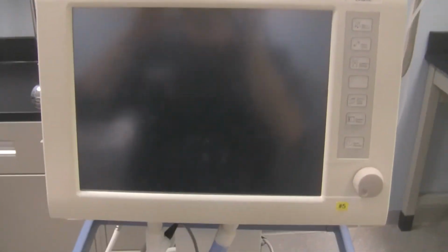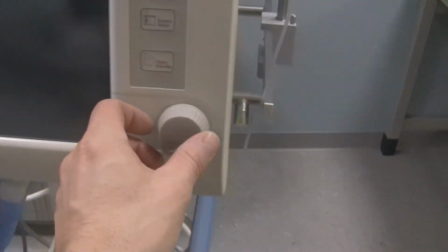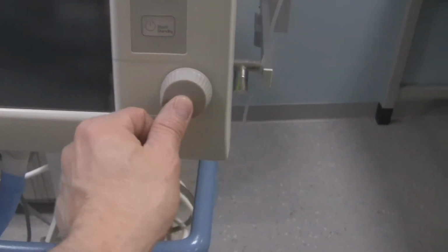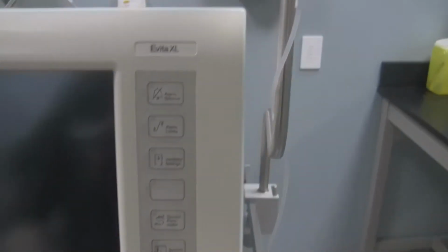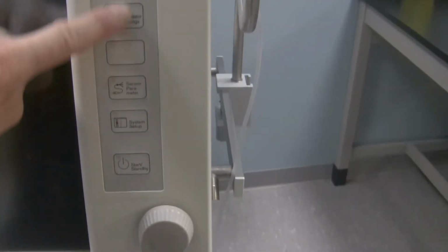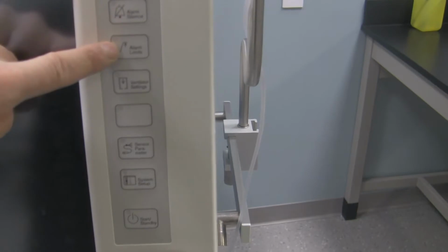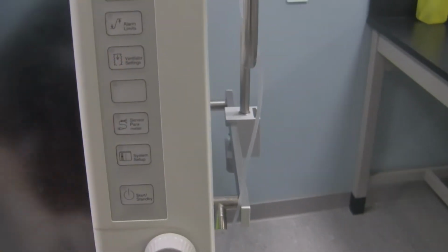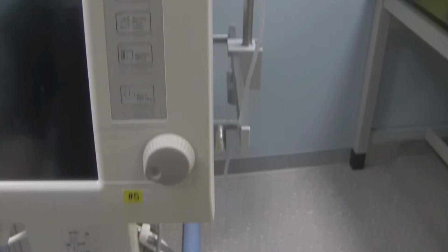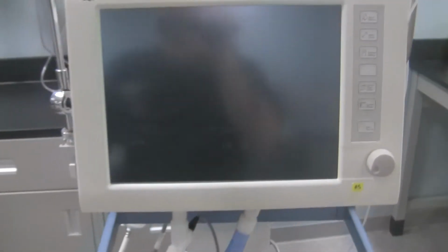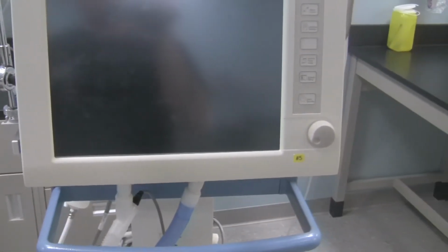This is the main screen right over here of the XL. You can see that it's pretty much a touch screen because you can't really see anything except my reflection inside there. A touch screen means you select what you need to and then set the value with this rotary knob right over here. This is the select the value knob, and you push it to confirm the value. There are also a bunch of buttons here that you can press for specific functions like alarm silence, alarm limits, the ventilator settings, which brings up your modes menu, etc. You'll become very, very familiar with the screens once you start using it.